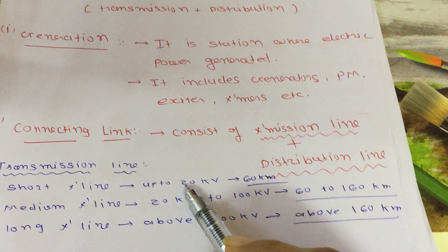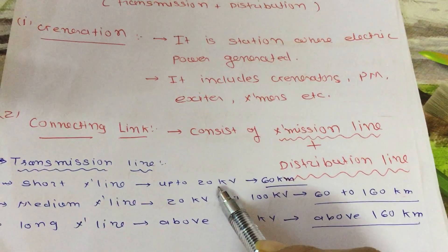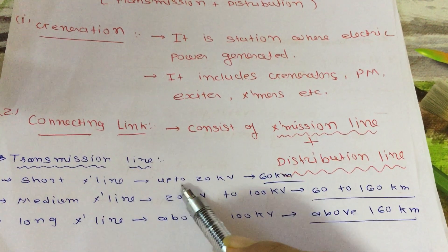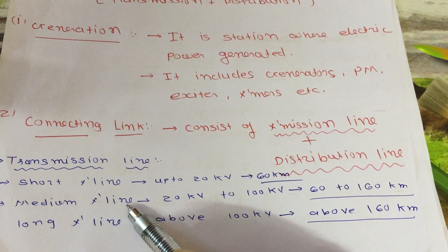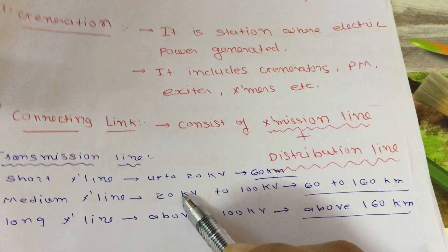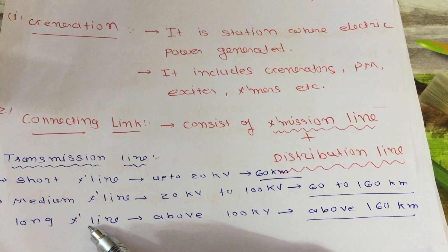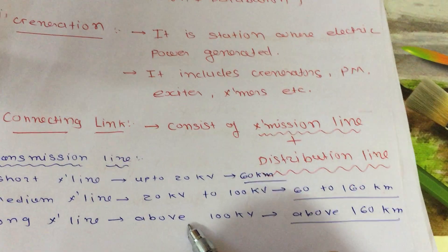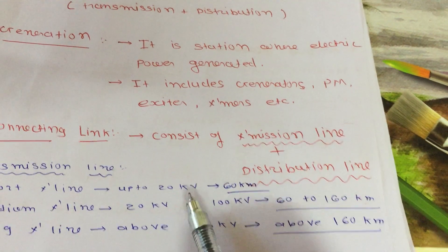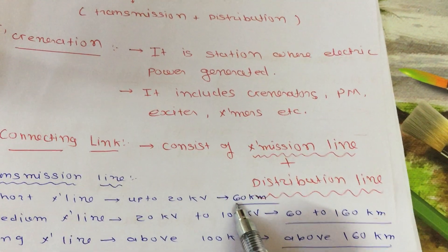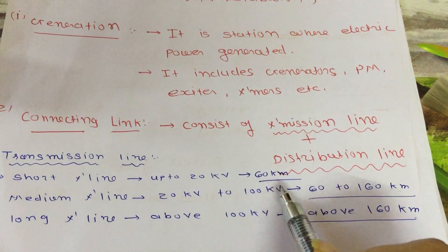If we classify by voltage rating: short transmission line is used for voltage up to 20 KV; medium transmission line is used for voltage between 20 KV to 100 KV; and long transmission line is used for voltage above 100 KV.